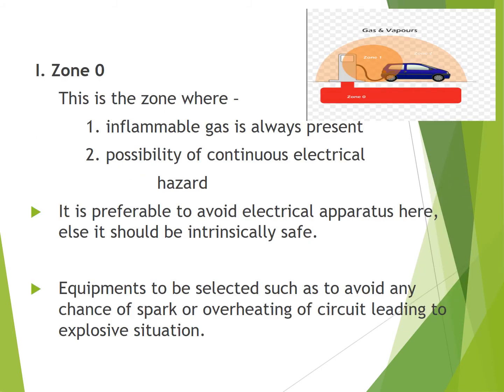Zone 0 is a zone where the inflammable gas is always present. It's very dangerous. Inflammable gas is always present, and there is a possibility of continuous electrical hazard. The selection of equipment for this area should be such that there is no chance of spark or overheating of the circuit which may cause an explosive situation. It is preferable to avoid the use of electrical apparatus in this area because the inflammable gas is always present. So this is zone 0.